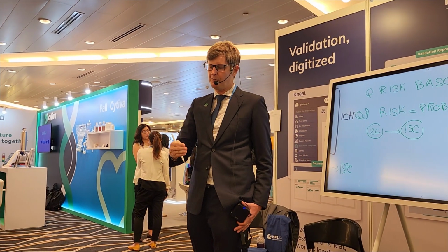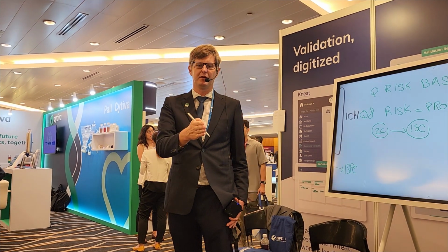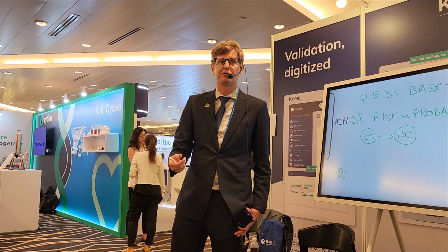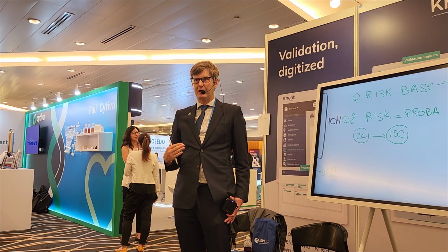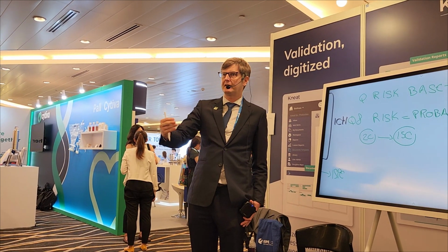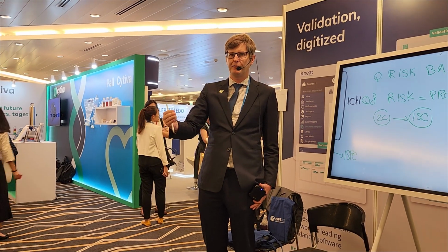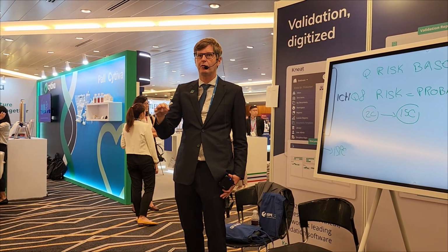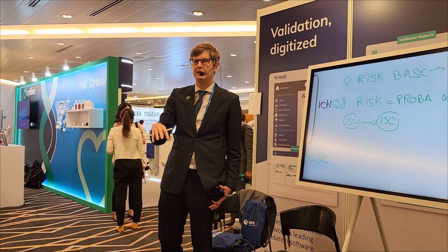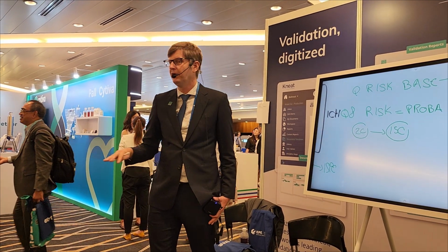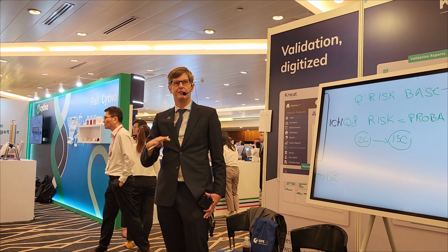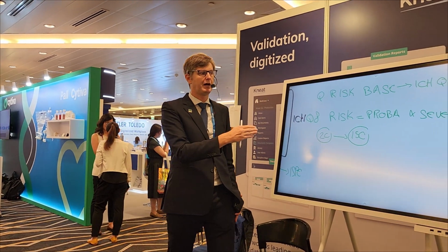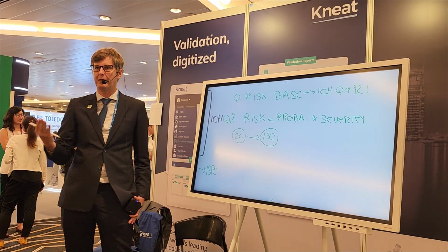So really pushing people more and more outside the room, moving from a grade A area where I'm literally above the product and what do I do if I sneeze, to a RABS area where I put a physical barrier so that I can have only a limited interaction above the product, to putting a glass door and a container so I can achieve that zero growth grade A area within the isolator. And as Shanshan explained last year, ideally we put a robot instead of a human so that I can automate it and remove a lot of variability, because sources of variability are also sources of probability of risk, right?